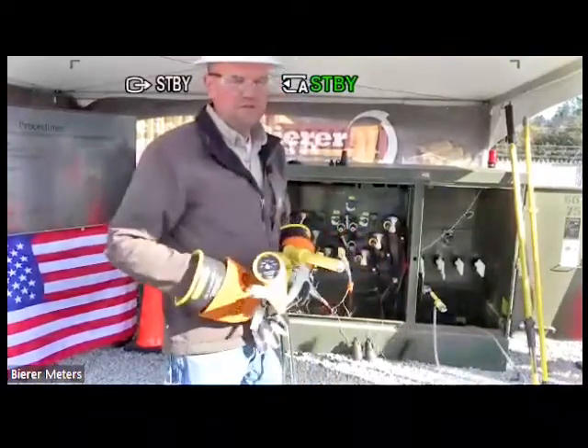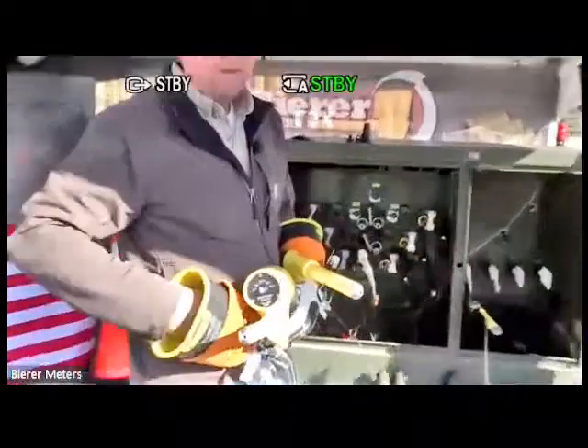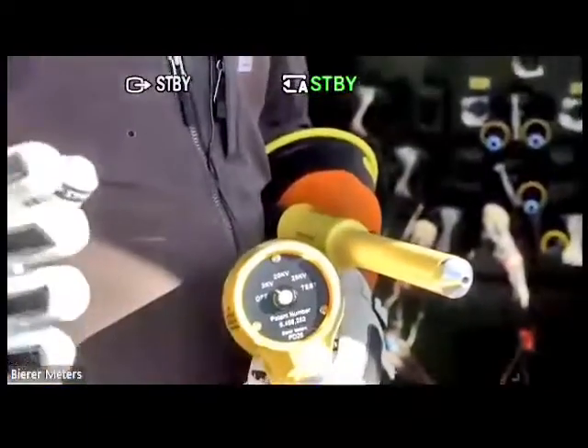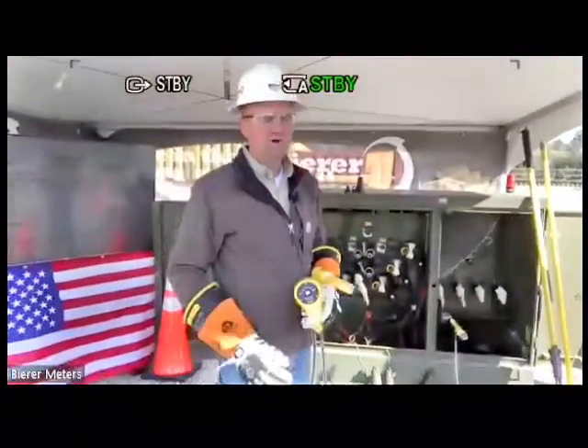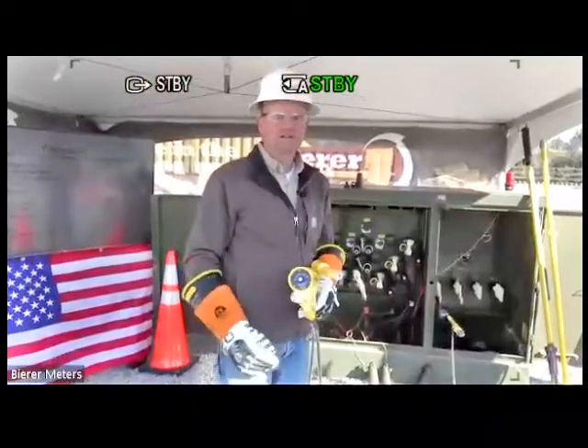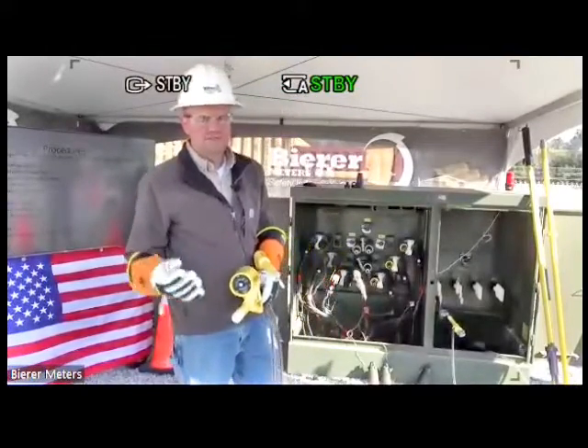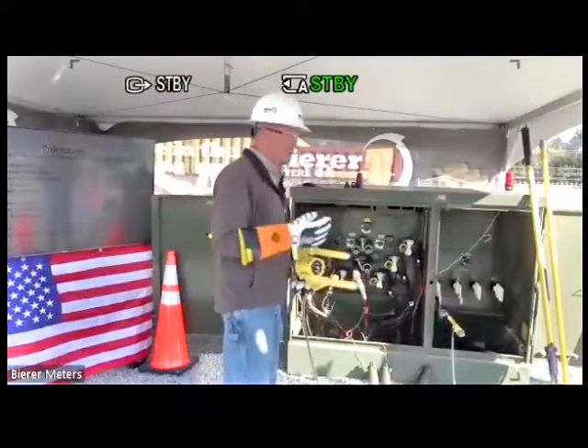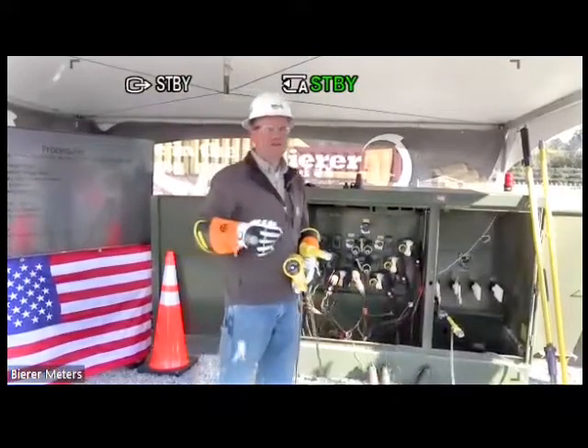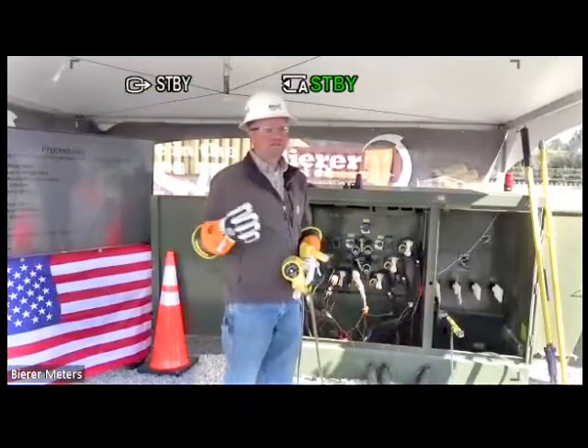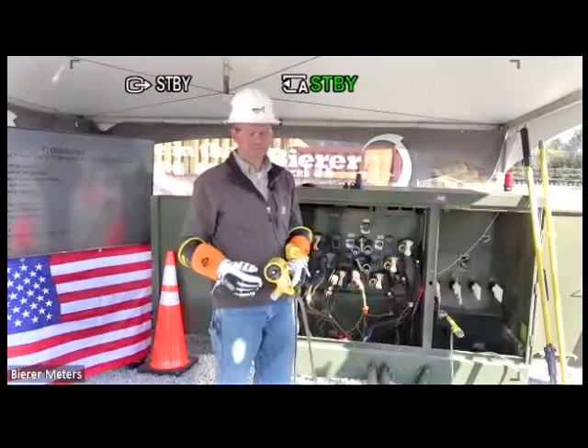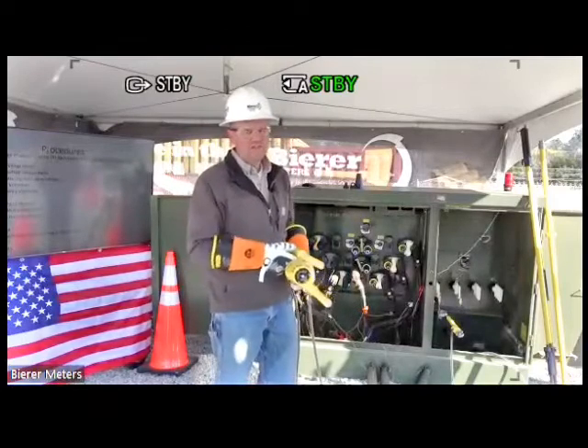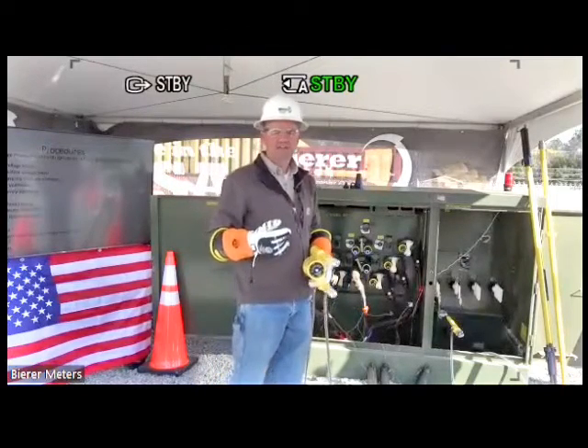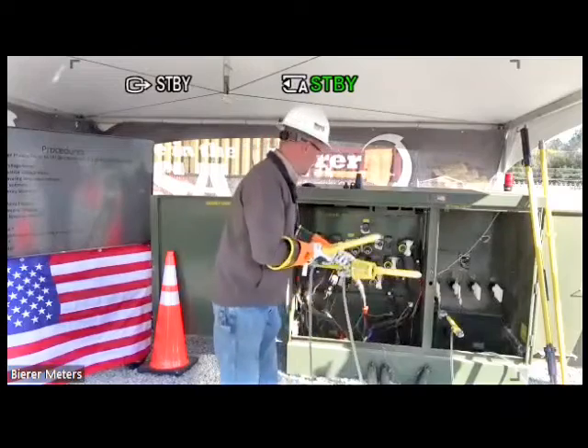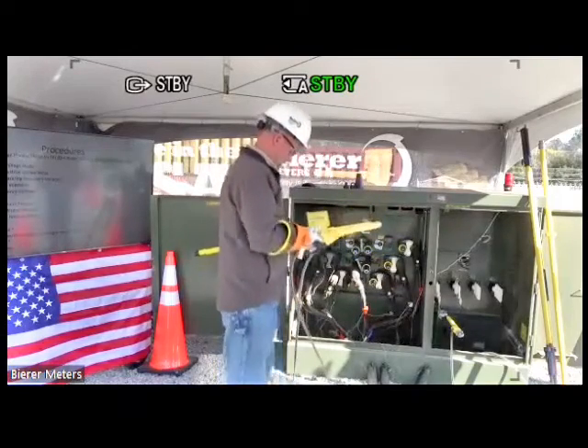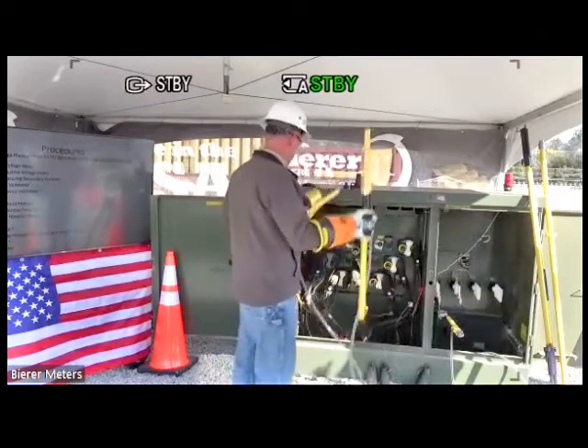And I want to do this in the 2 kV switch position. Depending on the manufacturer, capacitive test points could have anywhere from 200 to 300 volts roughly. Again, if it's failing, obviously less than that, but all the manufacturers are different, even the same manufacturer, and if they're different ages, it could vary substantially. So in the 2 kV switch position, it's going to give me the accuracy in order to phase and test the capacitive test points themselves.